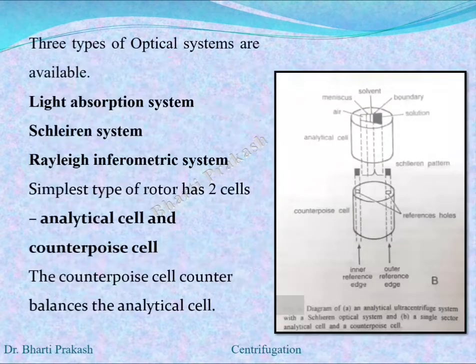There are three types of optical systems available: first is the light absorption system, there is the Schlieren system, and there is the Rayleigh interferometric system. The rotors in the centrifuge are also specially designed. The simplest type of rotor has two cells — the analytical cell and the counterpoise cell. The counterpoise cell balances the analytical cell.